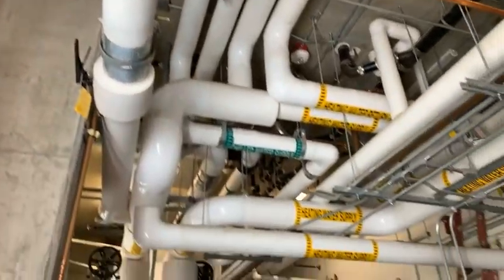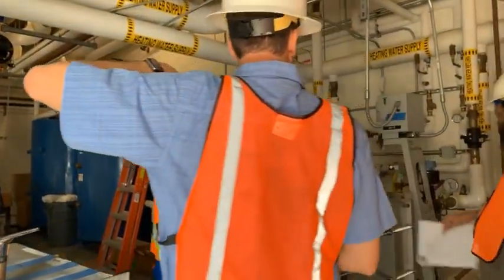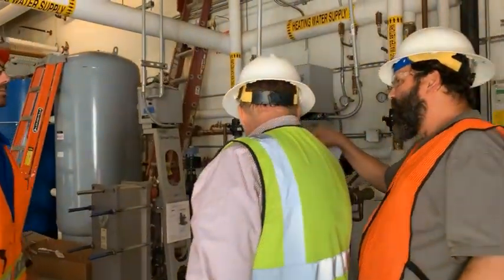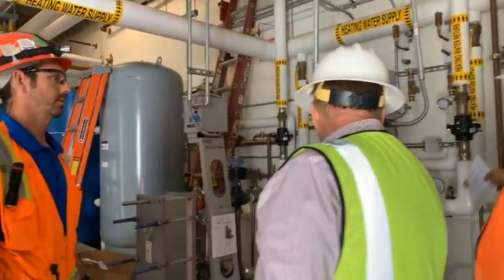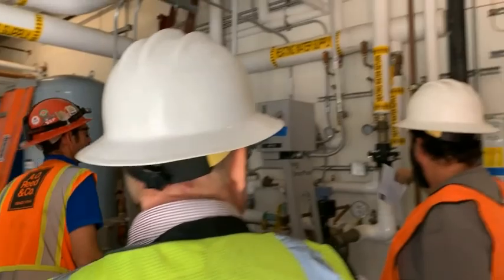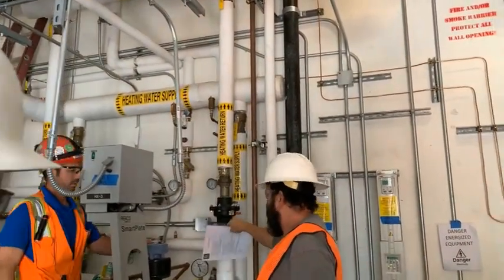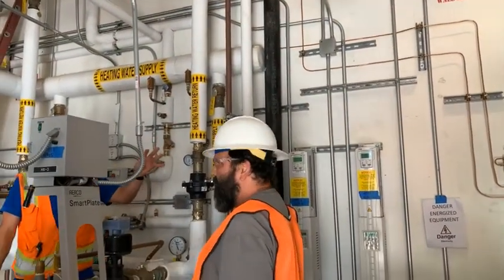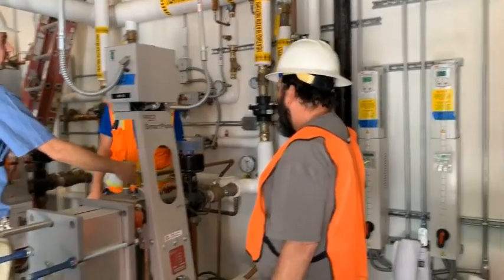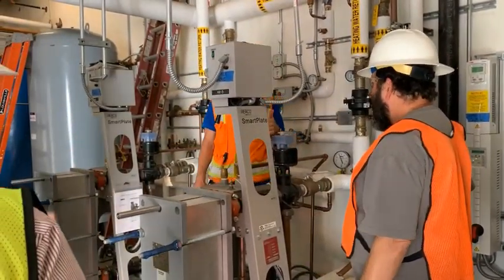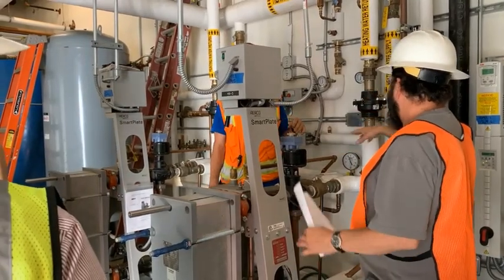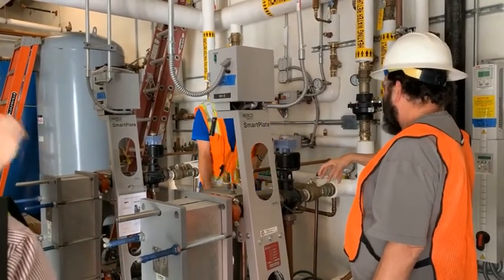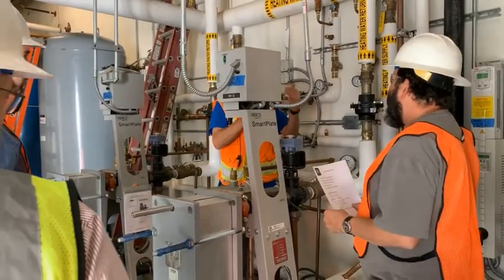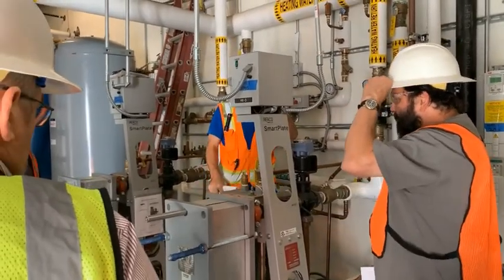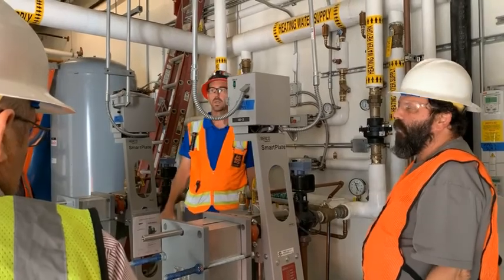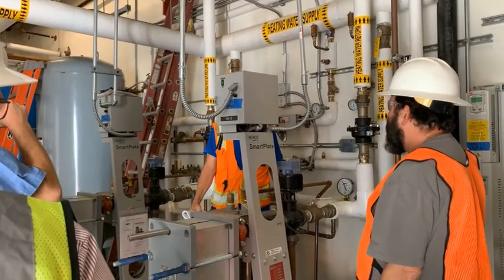Yeah, I've noticed that. So these make the domestic hot water. Yes. And why does this heating water return? Because that's how it heats this water. Yeah, we're using the heating hot water loop to make domestic hot water. I got you, domestic's on this side. You good? Yeah, it seems to me like the water's mixing here, but it's not. No, the water stays on different sides of the plates in the heat exchanger. It should never mix. Right. Potentially it could though.